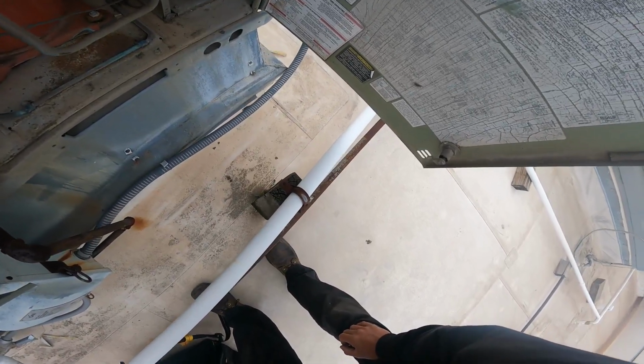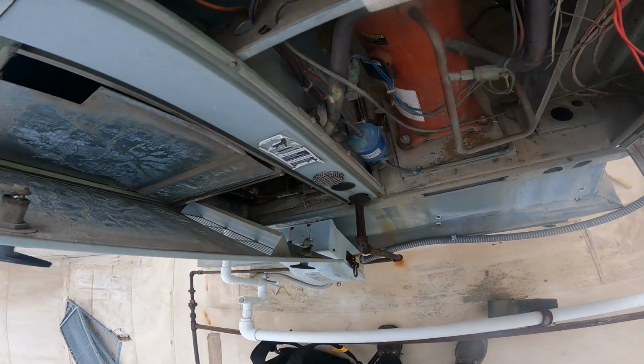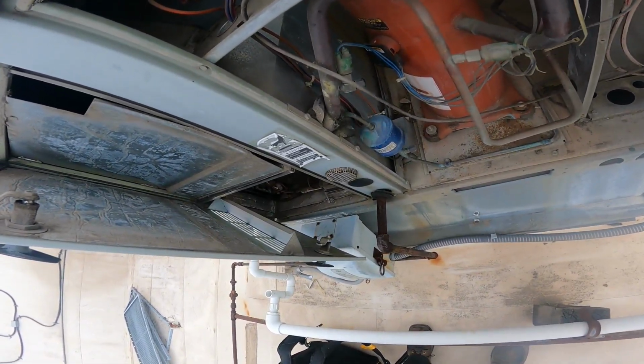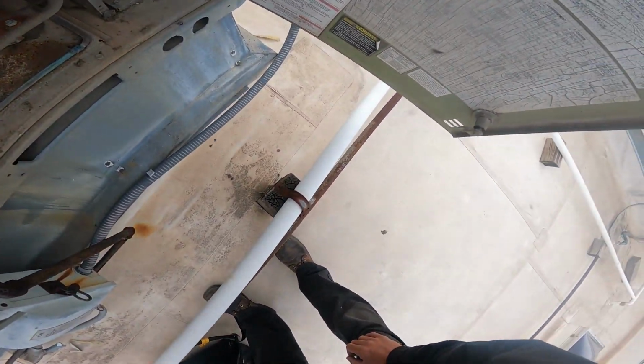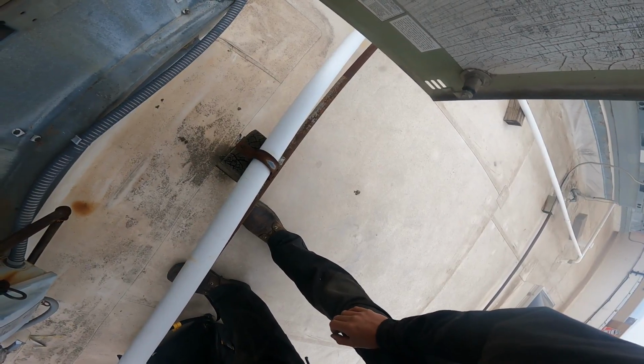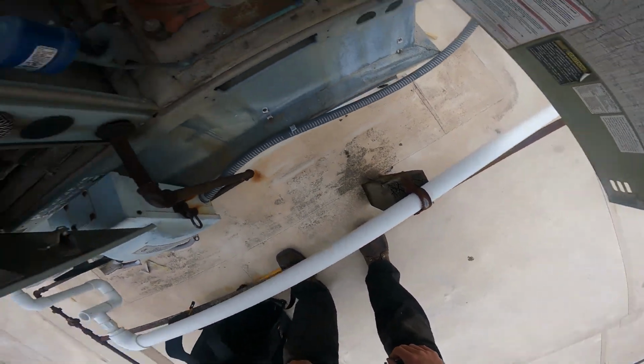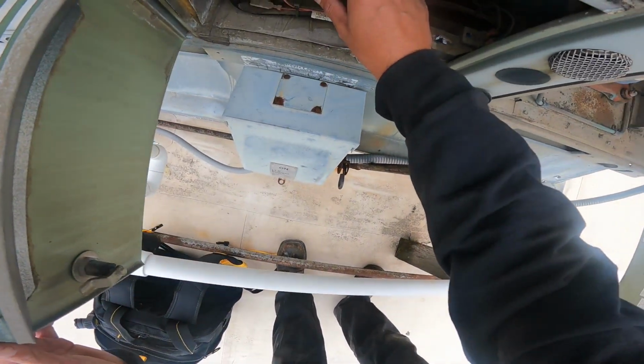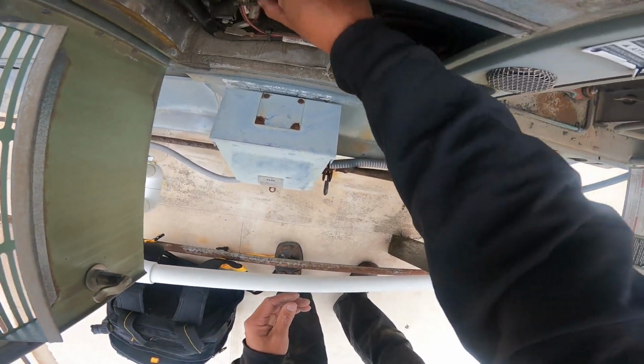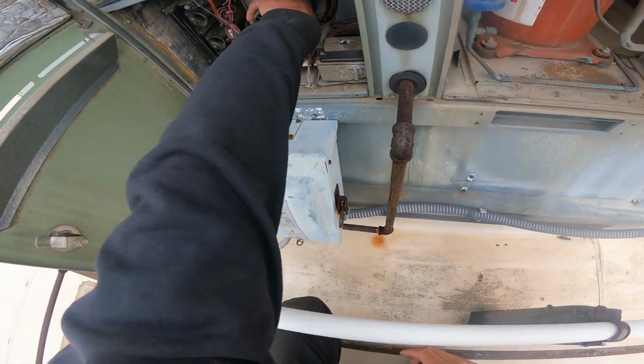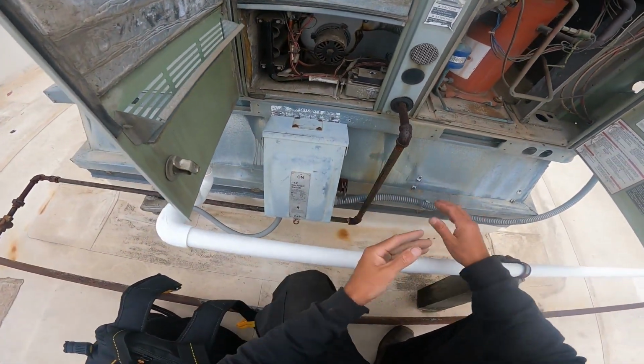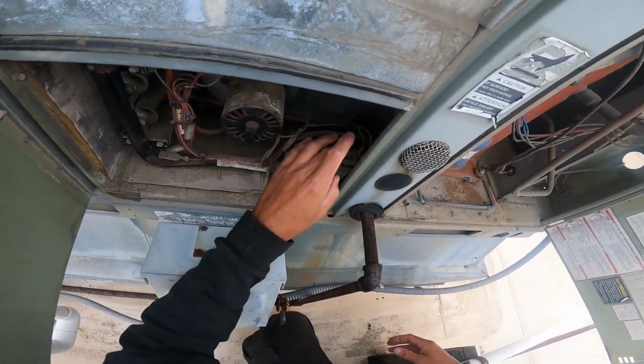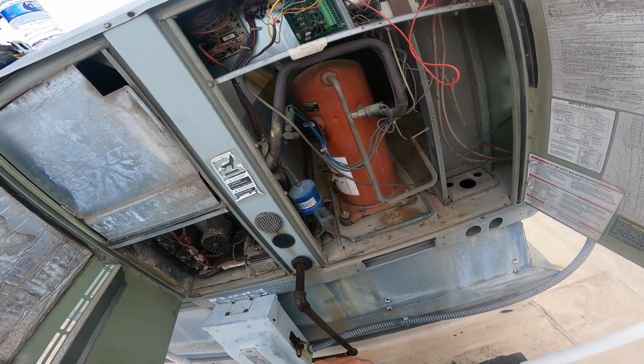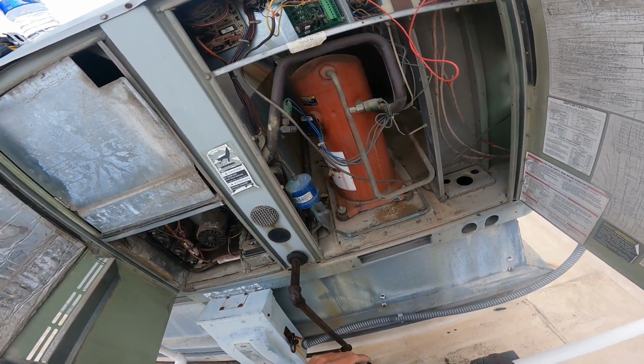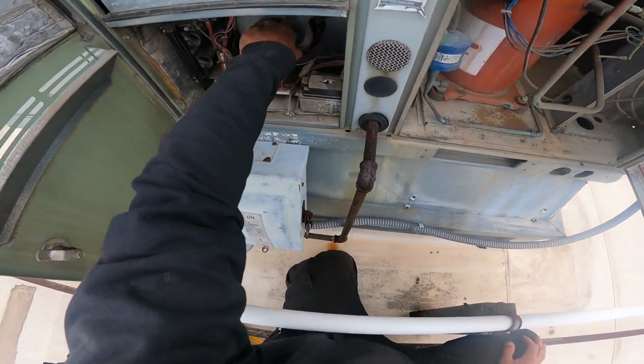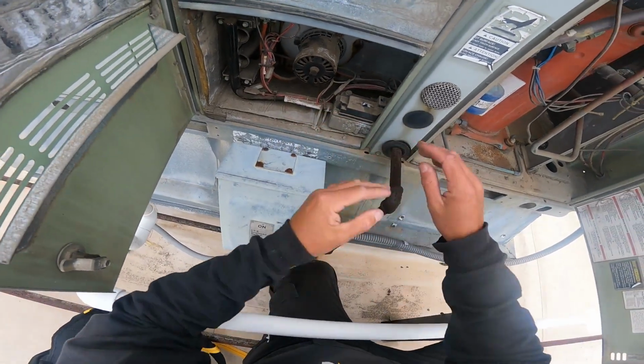And I'm getting flashing on my heat board. It is 1, 2, 3. 3 flashes on the heat board is pressure switch failure. That's weird, because the inducer never came on. Inducer never came on. The inducer is actually a little bit warm. So I wonder if it actually gave power to the inducer to try to turn it on when it was in heat mode. Let's see here. 1, 2, 3. 1, 2, 3. So it's only giving the 3 code. So that is our inducer motor. I guess we can try to figure out.